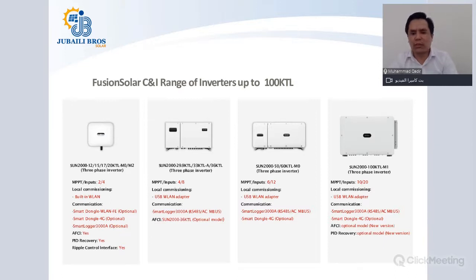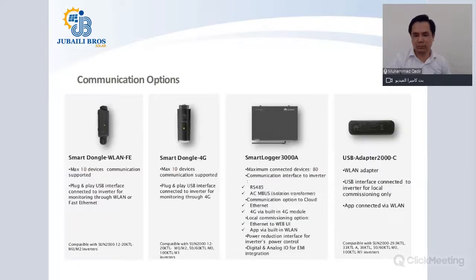So the fourth class of C&I inverter is SUN2000 100KTL-M1. This is a 10 MPPT inverter and with 20 string input. For local commissioning, you have USB WLAN adapter. For communication to do remote monitoring, you can have either a SmartLogger 3000A or a Smart Dongle-4G. AFCI is optional model coming with the new version, and PID recovery is also a built-in feature with the newer version. The newer version of 100 KTL will be introduced by the end of this year.